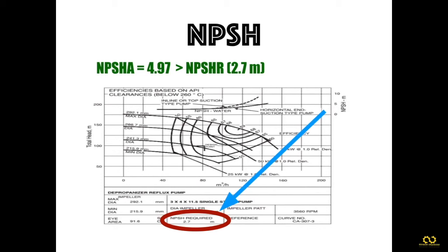By this method you can find the cavitation of a running pump. If it is less than the requirement of 2.7 meters, then the pump has high cavitation, which will affect pump performance. Immediately, the maintenance engineer should start troubleshooting by giving corrective recommendations to avoid cavitation.